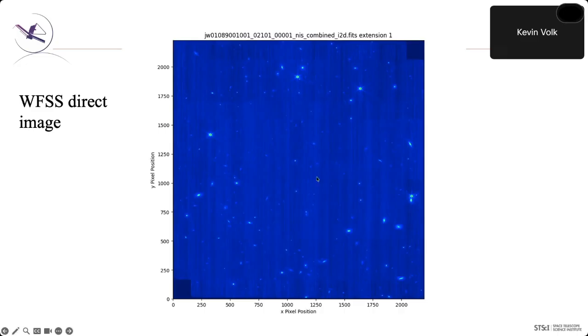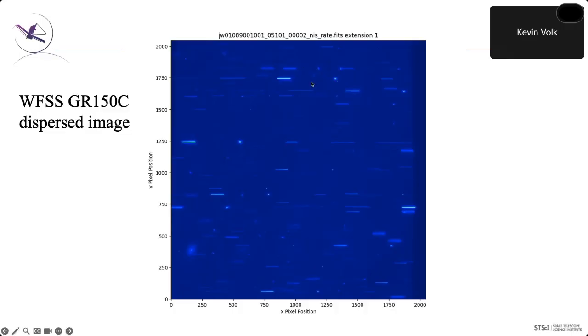This is the image of a field that we observed in this mode. This is what the direct image looks like, but when you put in the grism, you get all these spectra, multiple orders. So, for example, here's one source. We get a direct image analog. It's order 0. We get order 1, order 2, very faintly order 3, order -1. We're only calibrating order 1, and in one case order 2 for one filter, but all this other stuff is there, and these can contaminate the spectra that we want, but also we need to calibrate how these spectra change in position and their wavelengths at different positions in the field. So it can get complicated, but this field is not really crowded.